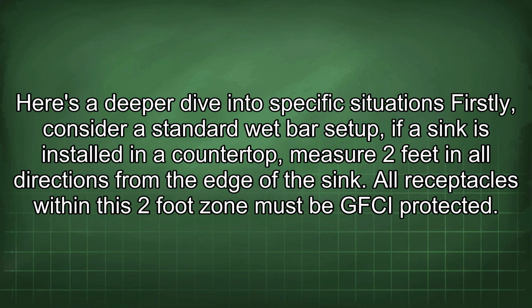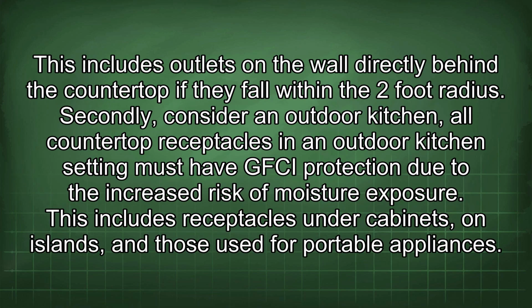Firstly, consider a standard wet bar setup. If a sink is installed in a countertop, measure 2 feet in all directions from the edge of the sink. All receptacles within this 2-foot zone must be GFCI protected. This includes outlets on the wall directly behind the countertop if they fall within the 2-foot radius. Secondly, consider an outdoor kitchen. All countertop receptacles in an outdoor kitchen setting must have GFCI protection due to the increased risk of moisture exposure. This includes receptacles under cabinets, on islands, and those used for portable appliances.